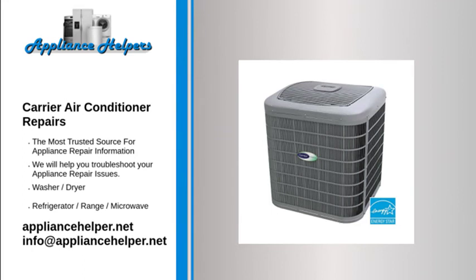Frozen evaporator coil. Air conditioner fans not working can be a sign of a frozen evaporator coil. The evaporator coil sits inside your home within the air handler unit, furnace or fan coil, pulling heat and humidity from indoor air as it passes through. The evaporator coil can freeze up as a result of indoor blower fan malfunction, low refrigerant charge, low outdoor temperatures, or other system malfunctions. Because a frozen evaporator coil can be the result of a blower fan stoppage or the reason the blower fan stops running, a frozen coil with fan stoppage should be diagnosed and remedied by your local Carrier expert.